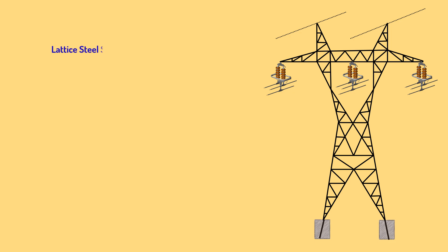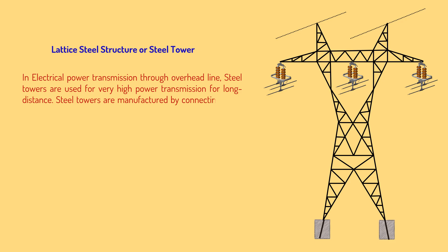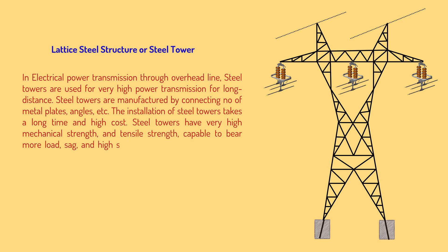Lattice steel structures or steel towers are used for very high power transmission over long distances. Steel towers are manufactured by connecting a number of metal plates, angles, etc. The installation of steel towers takes a long time and has high cost. Steel towers have very high mechanical strength and tensile strength, and are capable of bearing more loads with sag and high span. The steel tower footings are generally grounded by driving rods into the earth.